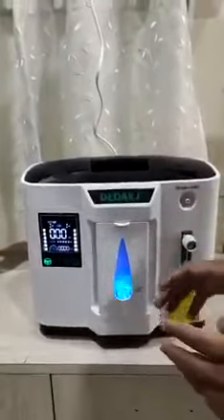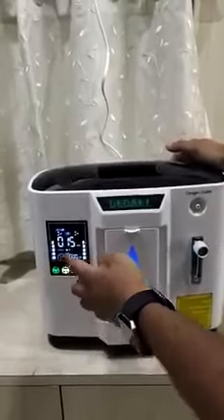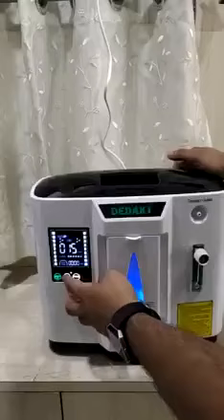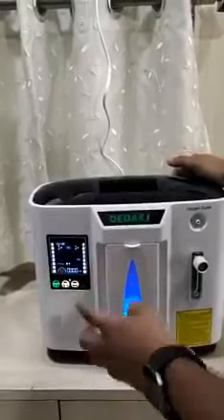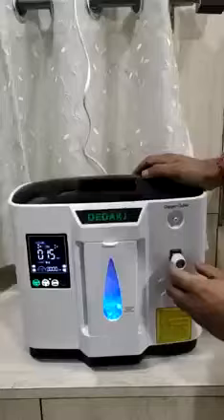So it starts generating oxygen. These are the timers — it will be on for 15 minutes, and if you want to increase, add further 15 minutes; if you want to reduce, reduce by 15 minutes. So it's in multiples of 15 minutes. Now you can see the oxygen is getting generated.